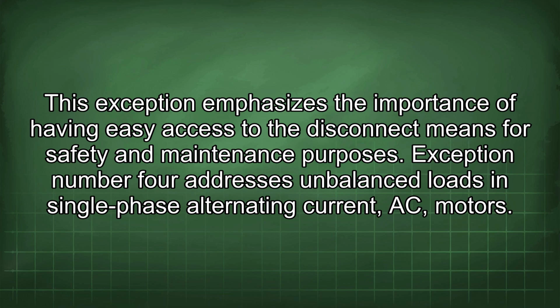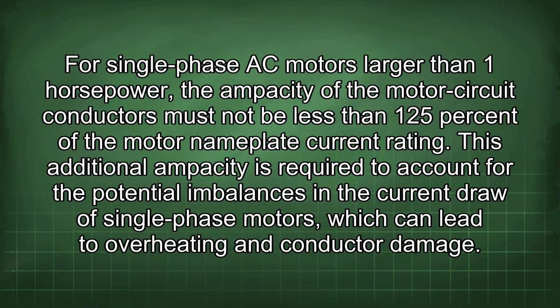Exception number 4 addresses unbalanced loads in single-phase alternating current (AC) motors. For single-phase AC motors larger than 1 horsepower, the ampacity of the motor circuit conductors must not be less than 125% of the motor nameplate current rating. This additional ampacity is required to account for the potential imbalances in the current draw of single-phase motors, which can lead to overheating and conductor damage.